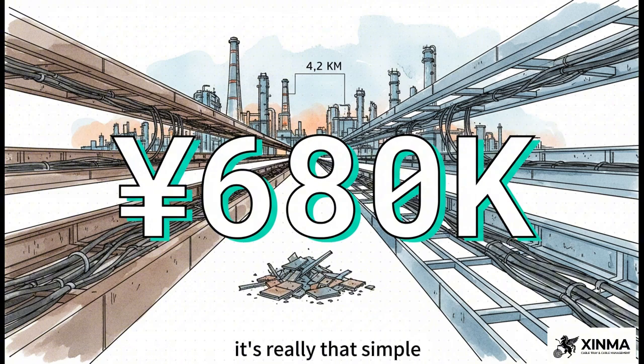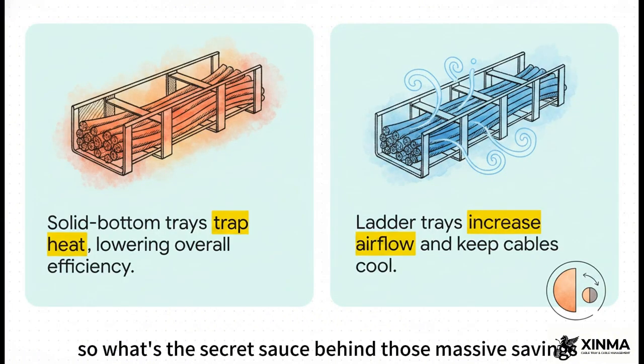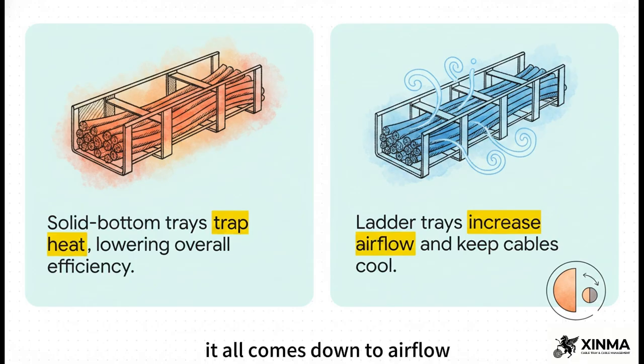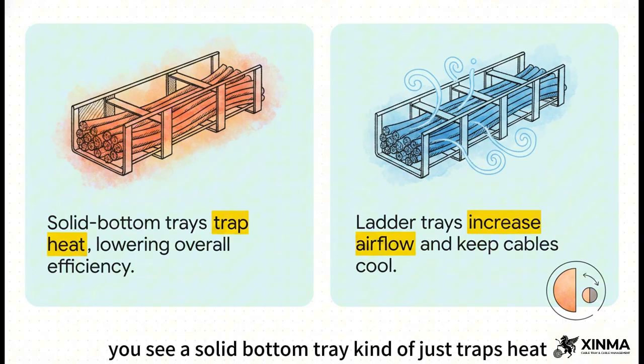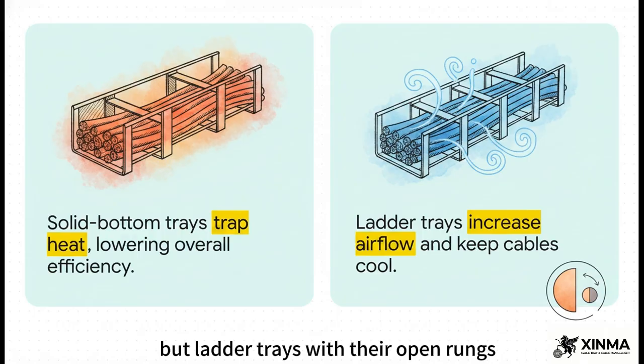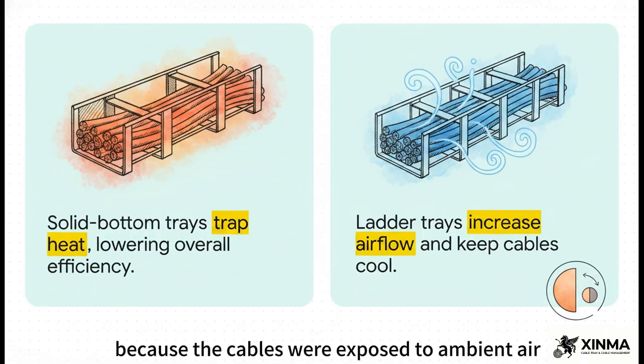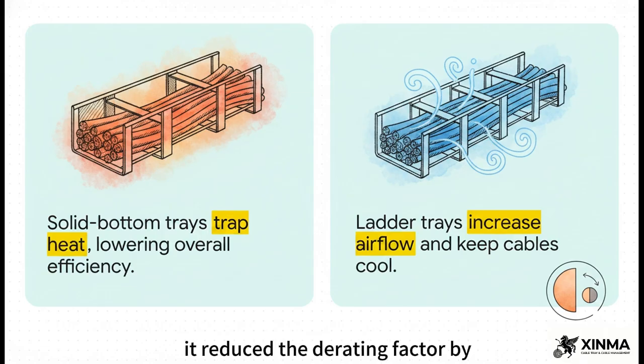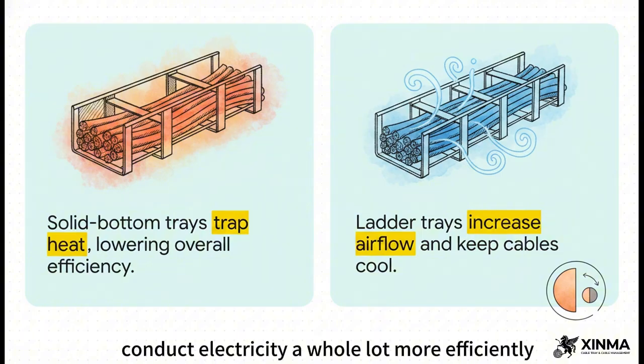It's really that simple. So what's the secret sauce behind those massive savings? It all comes down to airflow. A solid bottom tray kind of just traps heat, but ladder trays with their open rungs dramatically increase airflow. Because the cables were exposed to ambient air and running cooler, it reduced the derating factor by 12% on average, and cooler cables conduct electricity a whole lot more efficiently.